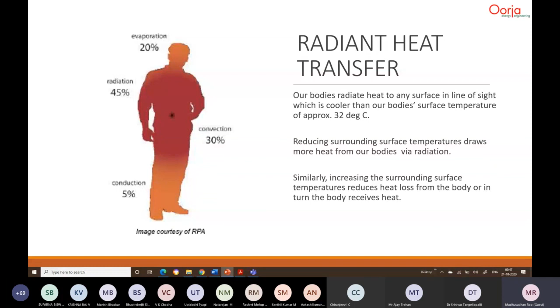Human comfort, we know, is dependent on these variables. But the temperature variables, if you see, we tend to ignore — we only take the air temperature in a space, measuring whether 24 degrees is there or not. But what we forget is a very important aspect of temperature, which is the mean radiant temperature. Mean radiant temperature is the average surface temperature of all the surfaces that the occupant is exposed to in a space. If you are in a room, the four walls, window glazing, ceiling, and floor are the surfaces — if you take the weighted average temperature of that, that would be the mean radiant temperature. And what we actually experience is the operative temperature.